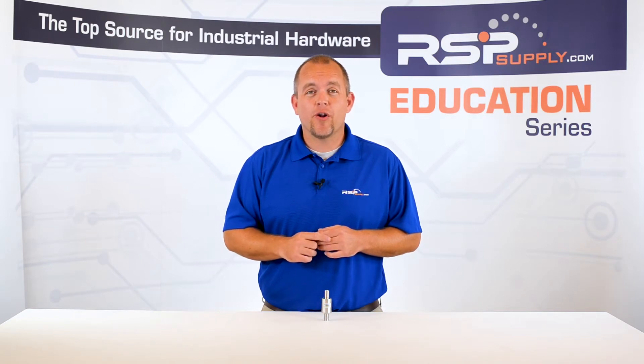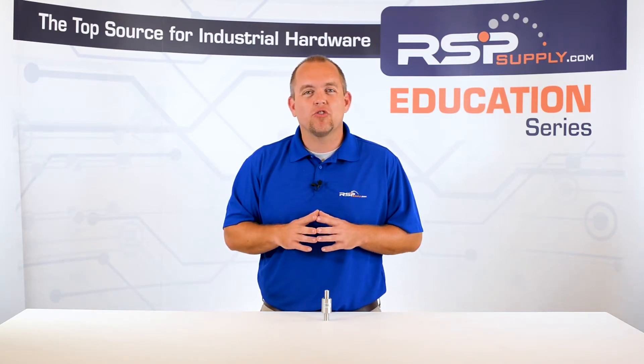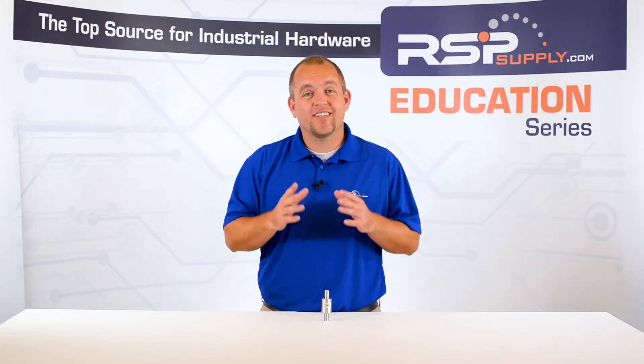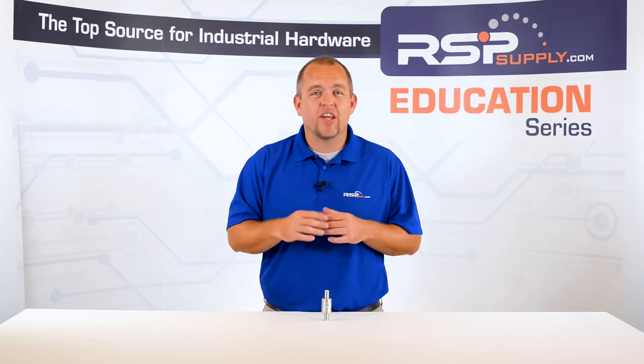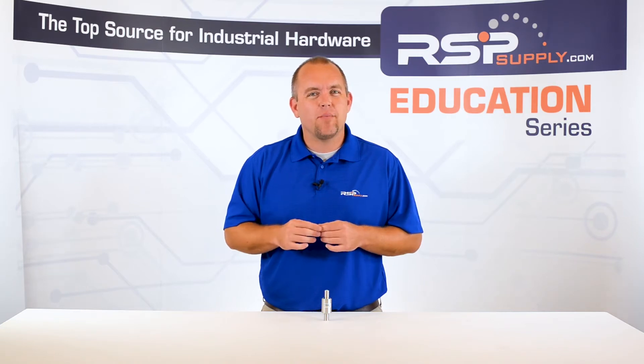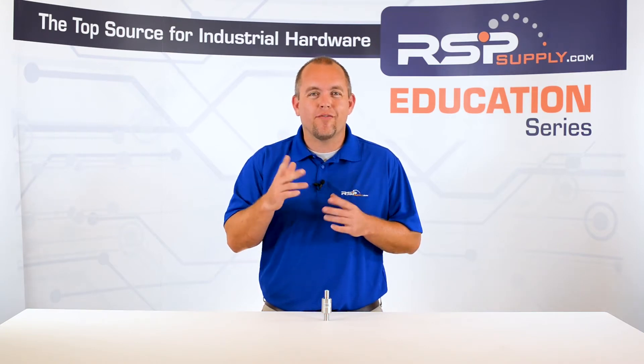More specifically, we are going to be talking about surge protection that is used for coax antenna cables and some best practices we use when installing these systems, especially relating to how to ground these surge devices. For the case of this video, we are using an industrial control cabinet example that will use an industrial radio to communicate with other remote sites. It is important to keep in mind that there are several methods that can be used when providing surge protection to a radio antenna, and the method we will discuss today is just one way that we have found to be effective.